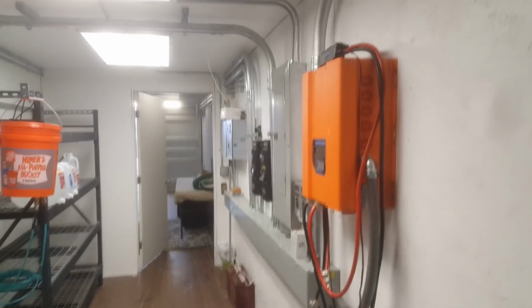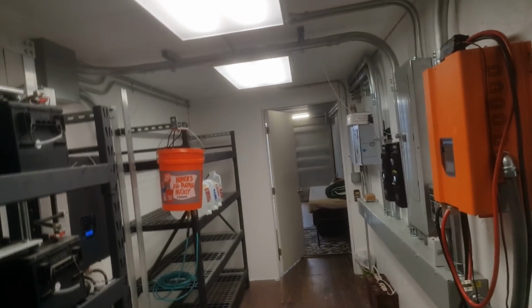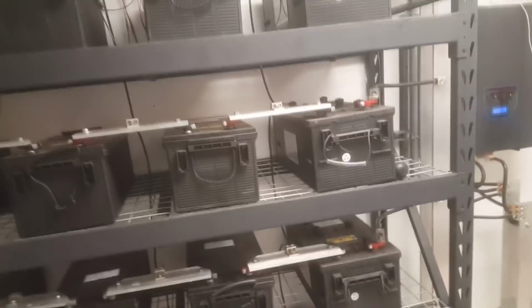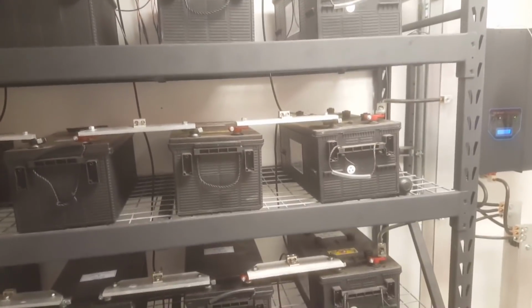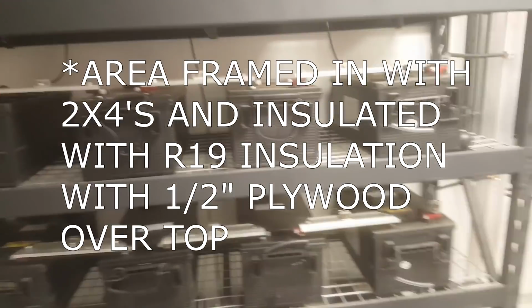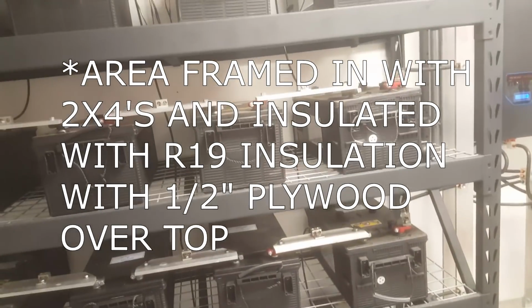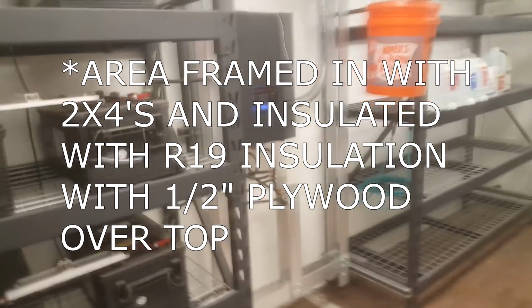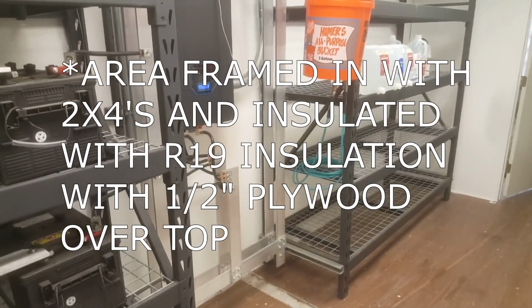All the electrical conduit was done by myself. I learned how to use a pipe bender. It's much cheaper than if you were to buy all the fittings and add couplers. It's also easier to pull the wire. Here I have an exhaust fan. It's approximately 1200 cubic feet a minute, and that is to pull out any hydrogen gases the battery makes. And also in summertime, I keep this room closed during the day. That way the heat stays out, and then at nighttime I open it up and turn on that fan and pull nice cool air in to remove the hot air from the room.